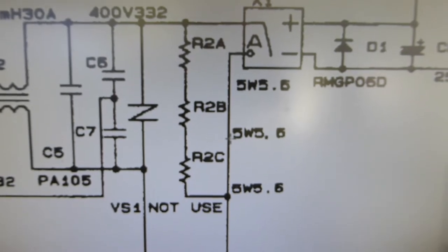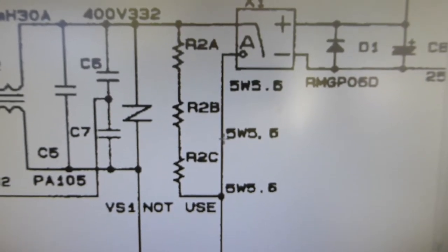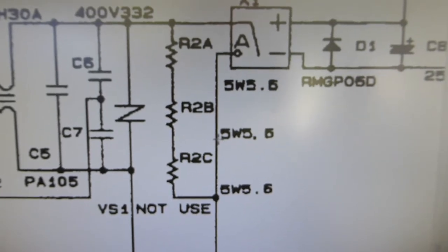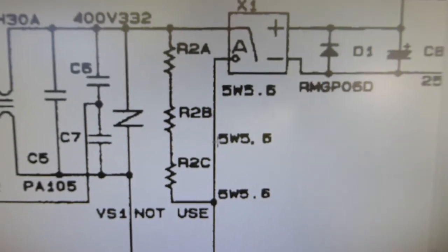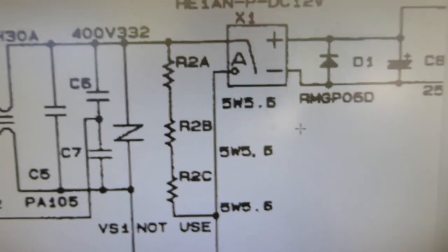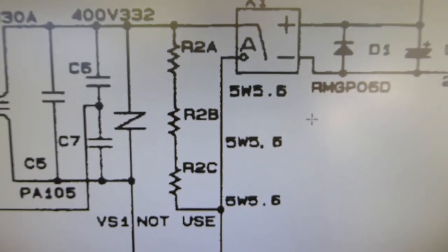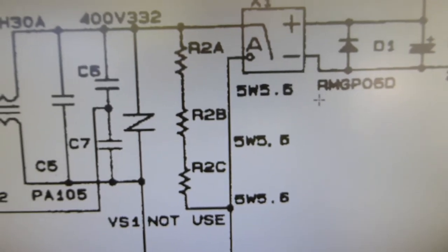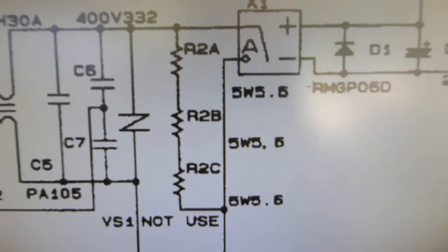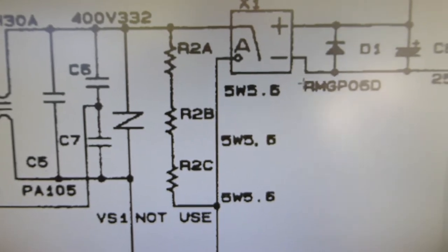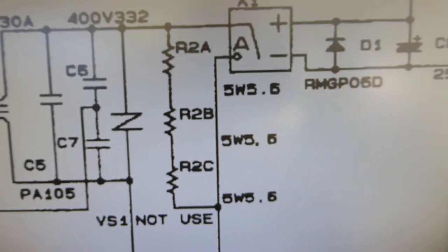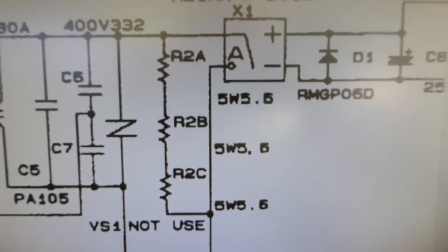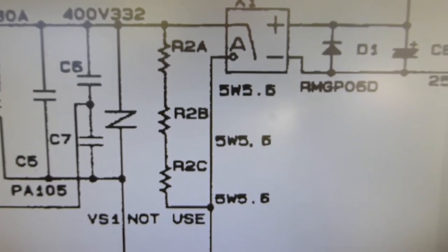And there are, I think, 10,000 microfarad smoothing capacitors in the output, i.e. 10 capacitors of 1,000 microfarad each. And that will give you a large inrush current. Normally, where you get a large inductive load or a large capacitive load and you plug that straight into the mains, there is always the chance that it will blow either the fuse or the trip.